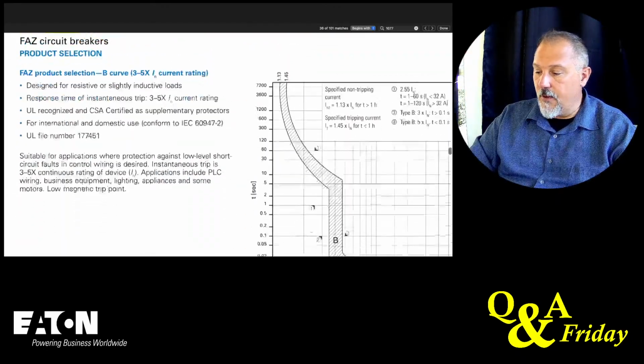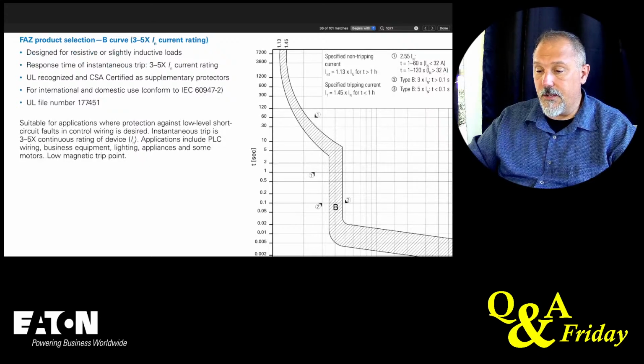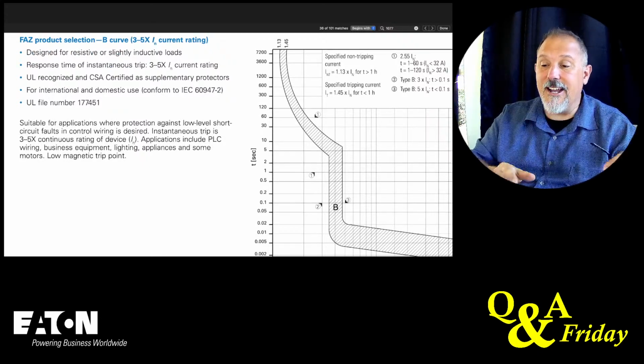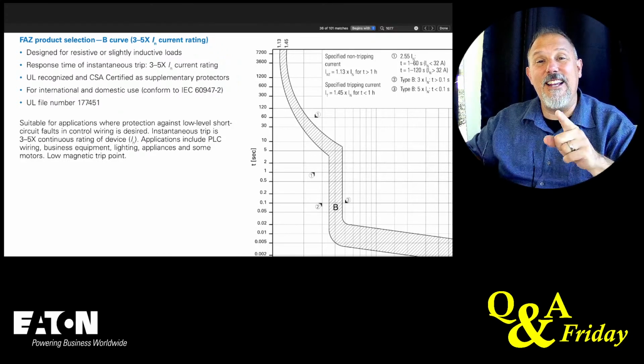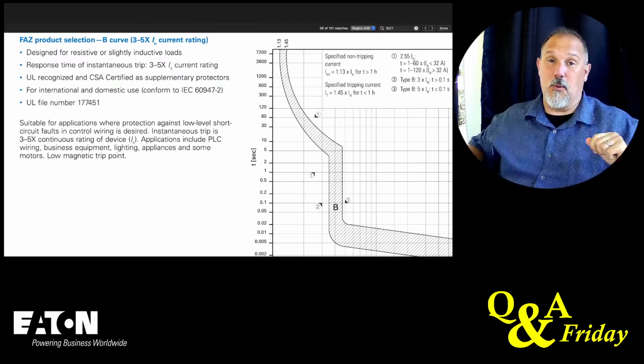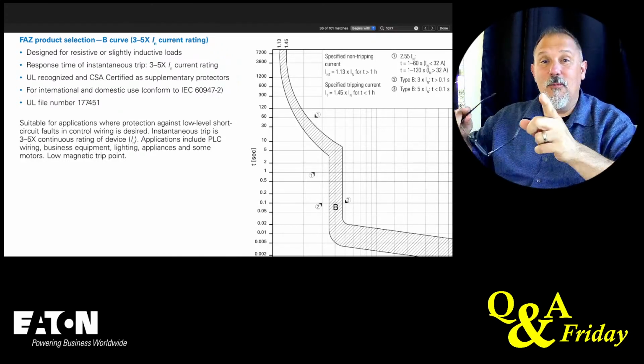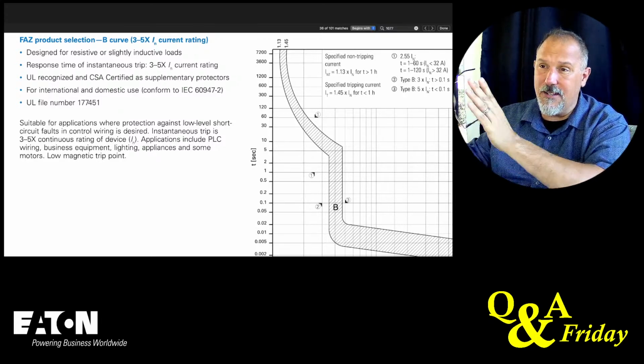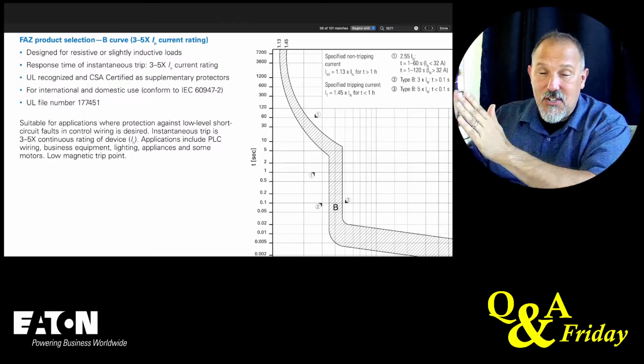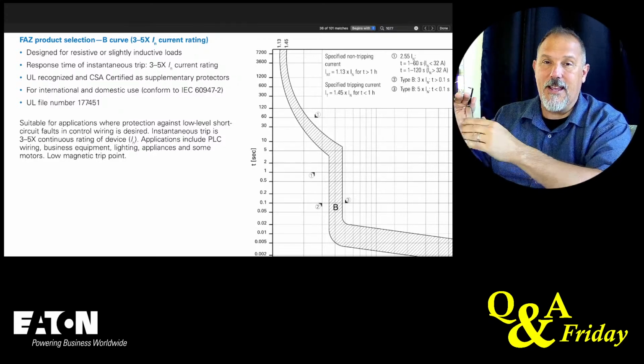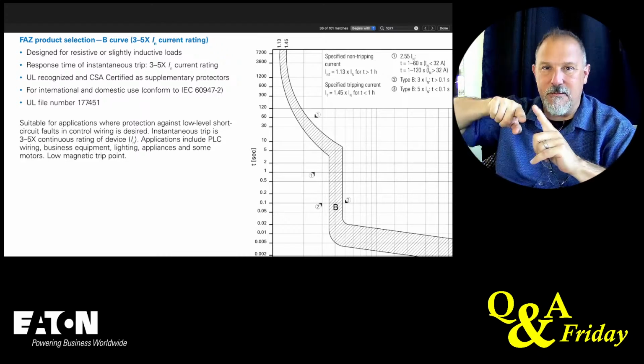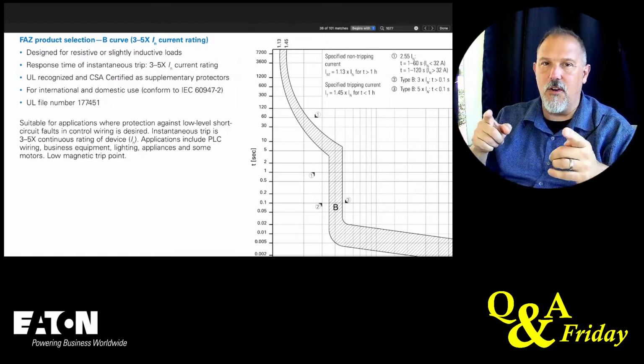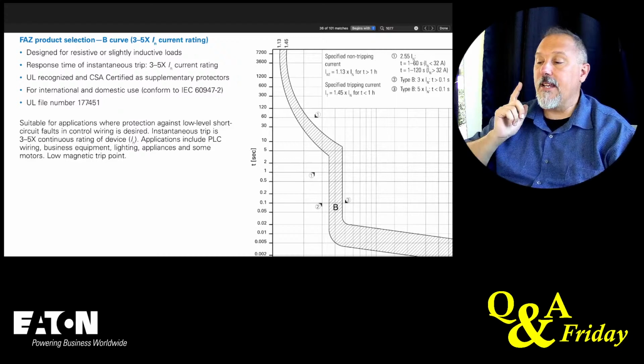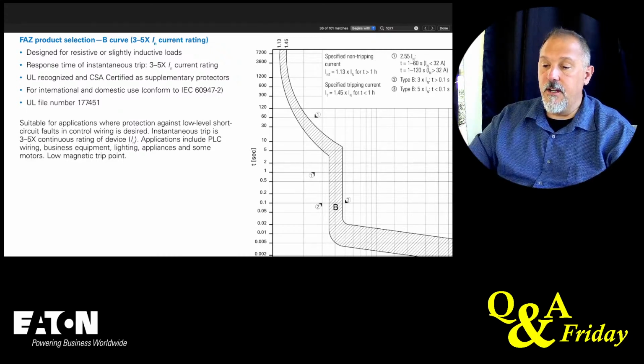1077 DIN-RAIL supplementary protectors. Look at that curve. So resistive or slightly inductive loads, designed for resistive or slightly inductive loads. Why is that important? Think about, and we're going to get into that when we talk about interrupting ratings, the X to R ratio. Okay, that DC offset, that asymmetrical sine wave stopping the flow of that first half cycle is the hardest part for some of these overcurrent protective devices.